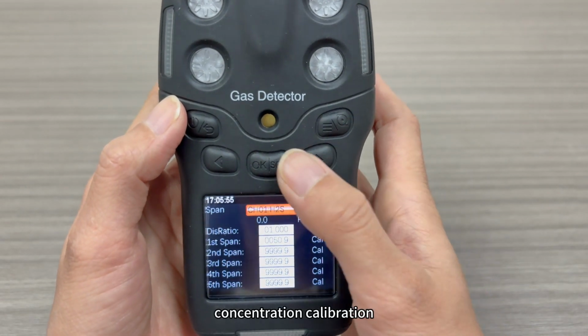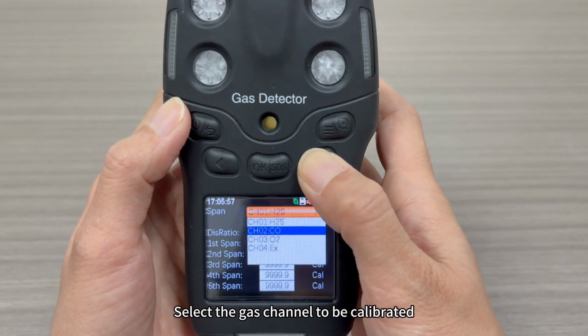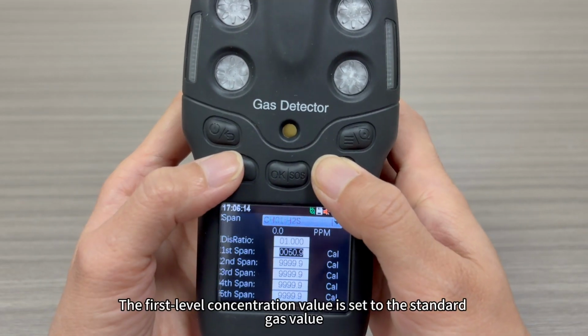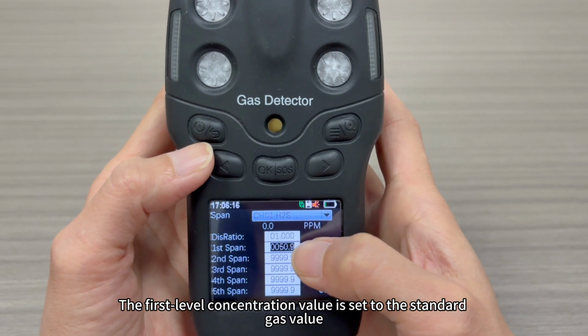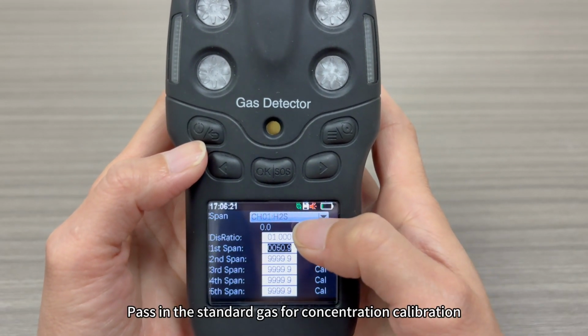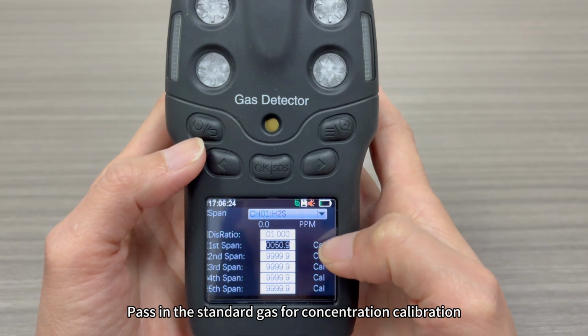Concentration calibration. Select the gas channel to be calibrated. The first level concentration value is set to the standard gas value. Pass in the standard gas for concentration calibration.